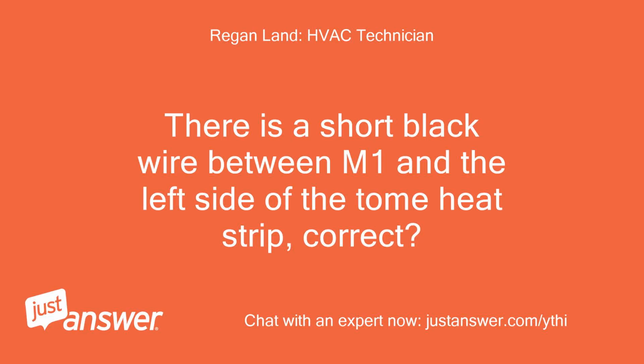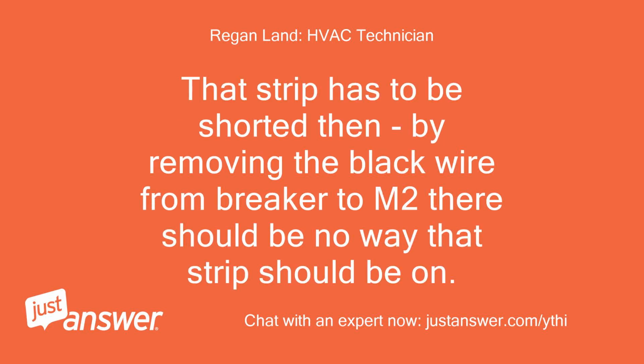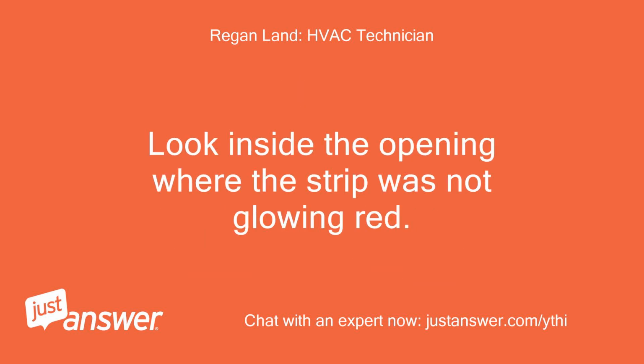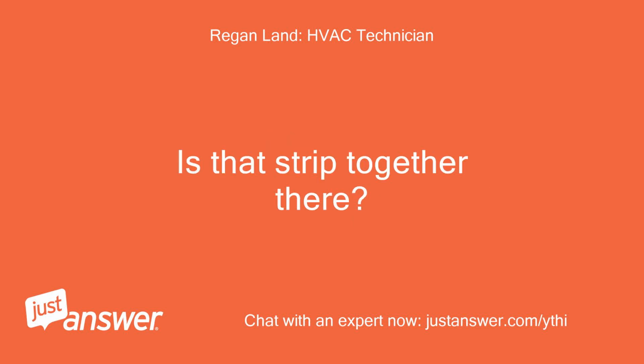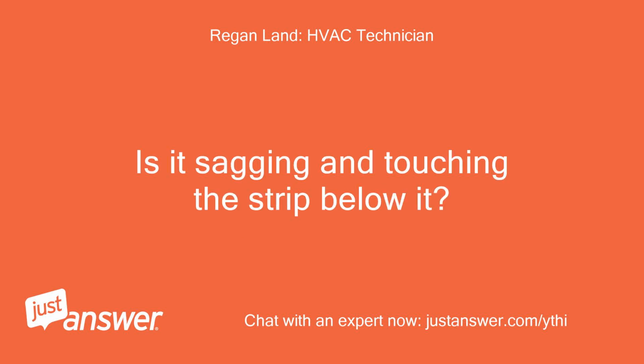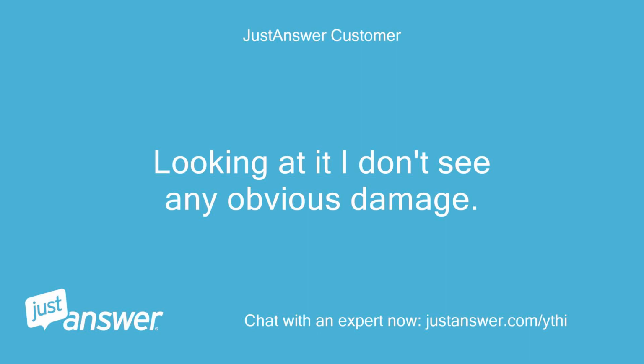There is a short black wire between M1 and the left side of the top heat strip, correct? That strip has to be shorted then. By removing the black wire from breaker to M2, there should be no way that strip should be on. Look inside the opening where the strip was not glowing red. Is that strip together there? Is it sagging and touching the strip below it? Looking at it, I don't see any obvious damage.